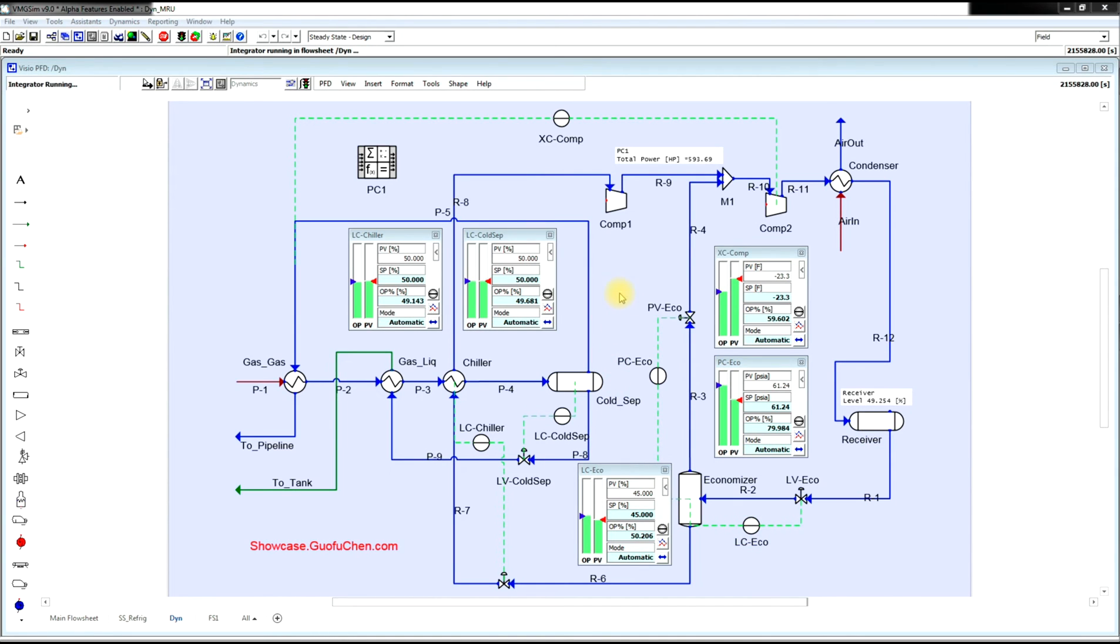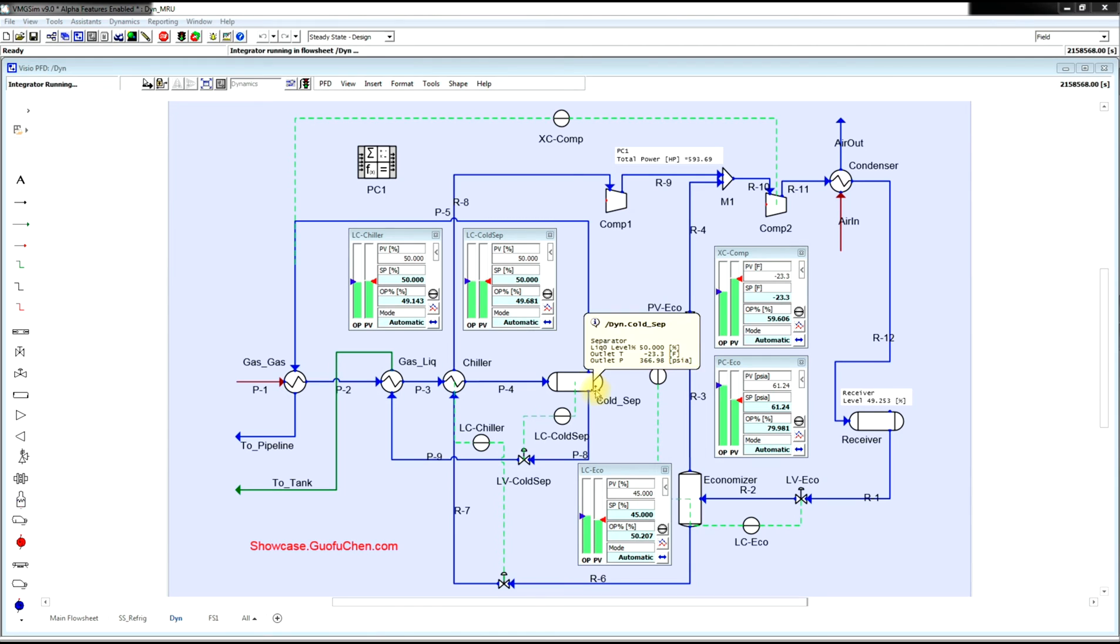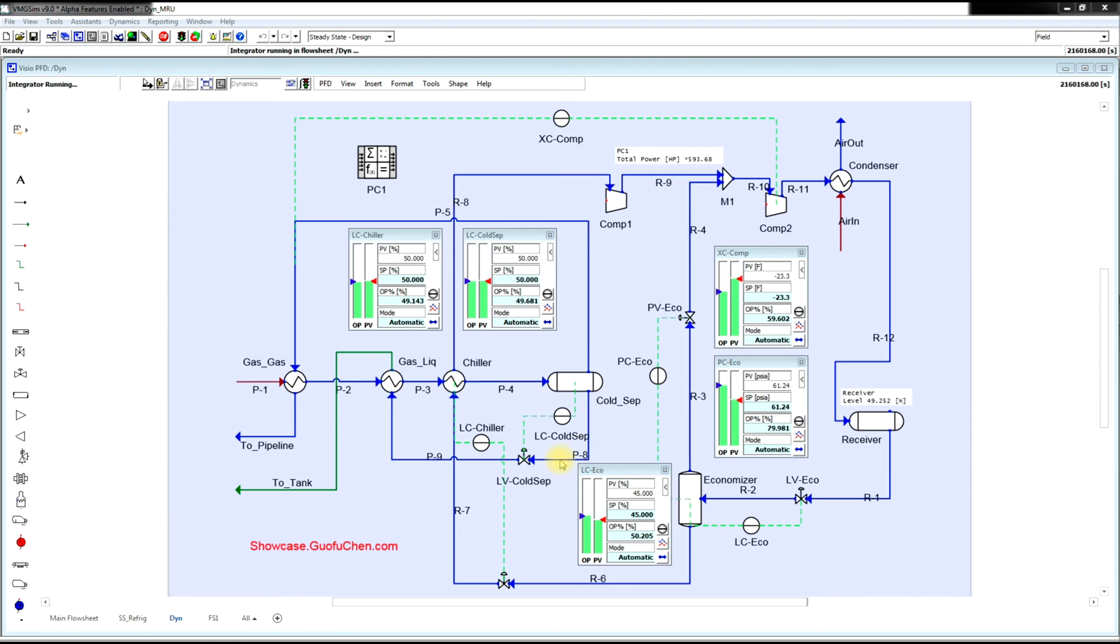For this particular project, we have a total of five controllers. First, we need to have a liquid level controller to control the cold separator liquid level by adjusting the valve at the outlet of the cold separator. Second, we need to have a liquid level controller in the chiller by adjusting the valve in front of the chiller.